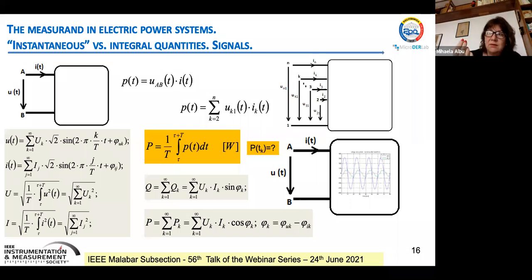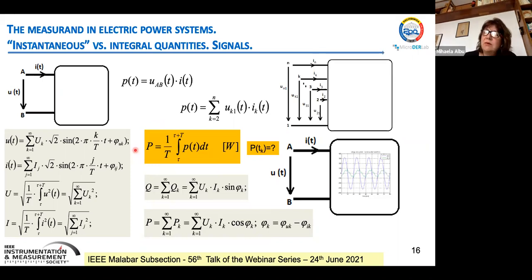If we report a value of the active power measured at a moment tk, we have to say what it represents. It represents the average of the so-called instantaneous P of t. No one speaks about this, but it's the active power calculated or estimated over a time interval, and reported later, at the end of that time interval, or whenever. So this value has no meaning if we don't know what power this actually is, and over what time window it was calculated.